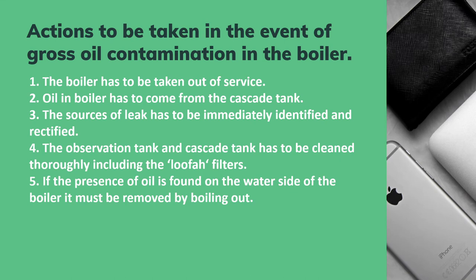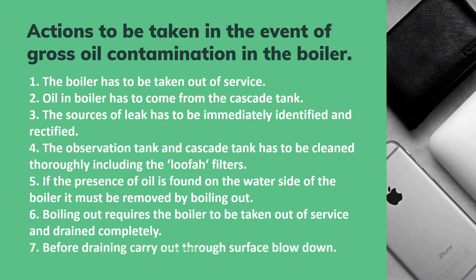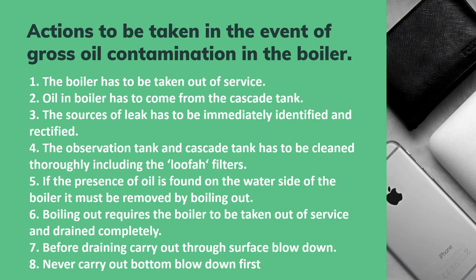If oil is found on the water side of the boiler, it must be removed by boiling out. Boiling out requires the boiler to be taken out of service and drained completely. For this, we have to drain the boiler completely and flush. Before draining, carry out a thorough surface blowdown. Never carry out bottom blowdown first, because doing so will cause the oil floating on the boiler water surface to form another layer.